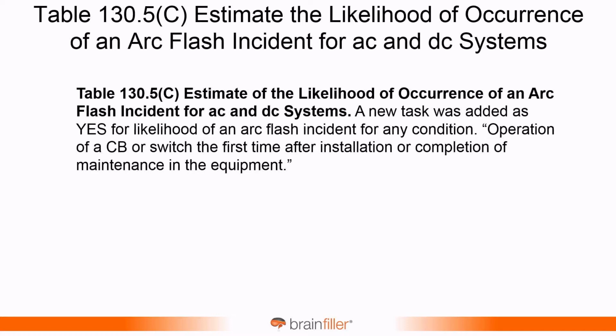Estimate the likelihood of occurrence of an arc flash incident for AC and DC power systems. This is new. This is a new addition. Some people have been talking to me about this, and let me explain what this is about. So we have these tables, and I mentioned the tables. The first version of these tables was introduced in the 2015 edition, and it lists certain tasks. And then it lists, it didn't start out this way, but now it says likelihood of an arc flash, yes or no. And so there's a lot of different tasks in there. And in general, if you have equipment where all the covers are in place, normal operation, and just operating it, it's considered basically not a high likelihood of an arc flash. But there's one in there now that is.